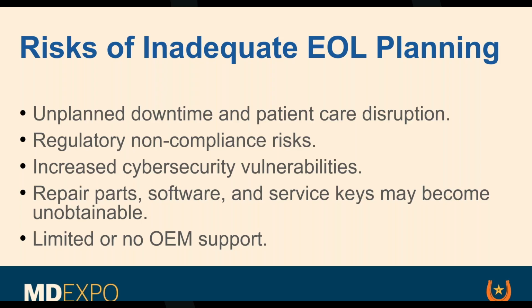So AIAT is assemble, install, adjust, and test. For a couple of decades now, it's been a rule that original equipment manufacturers must provide at a reasonable cost to reproduce, meaning if it's a sheet of paper, they can't charge you $300 for it. If it's a thumb drive, they can't charge you $5,000. It can be 200 bucks, but it can't be $5 grand. They must provide you, the owner of the equipment, and that's very important. So if you're a third party servicing equipment at a hospital and you're not employed by that hospital, you need to have a letter of agency, because it is the owner of the equipment that's entitled to AIAT entitlements.